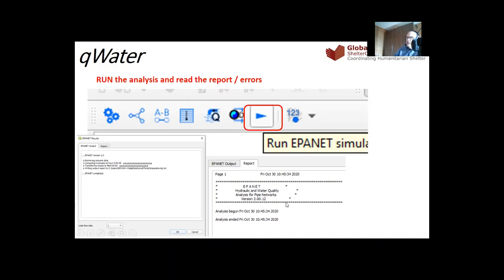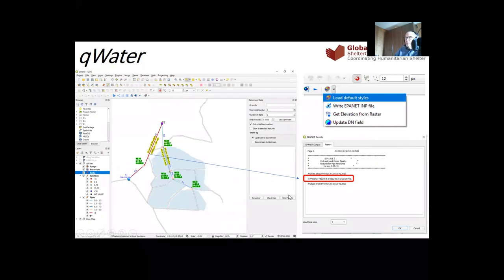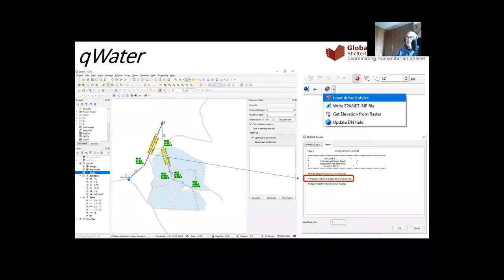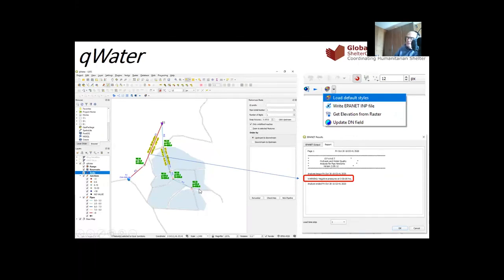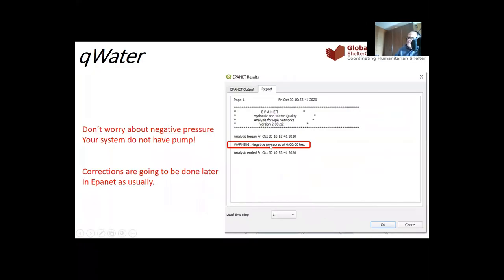As you can see, I did not add a pump or any pattern because this plugin does not yet accept those. Run the simulation. If you are lucky, everything is fine. If not, check what the problem is. If there is no pressure, don't worry — of course we don't have enough pressure without a pump; the system is incomplete. You can load the default style to see pressure everywhere, friction losses on pipes, and pipe velocity. But pipe velocity isn't very meaningful without a pattern.